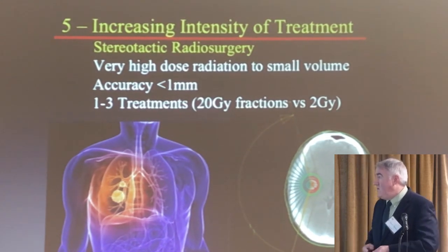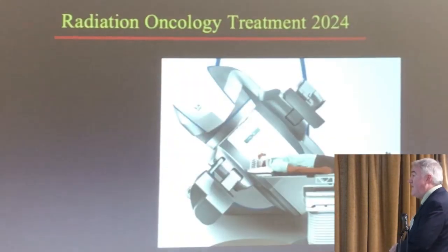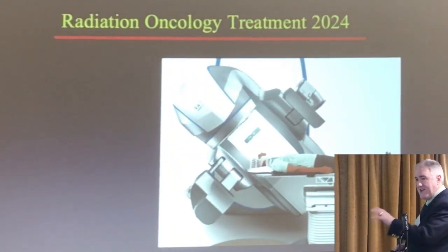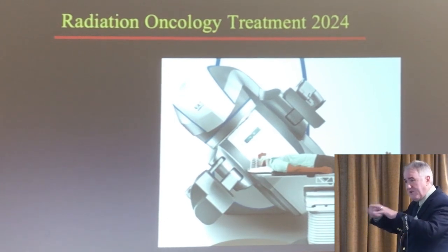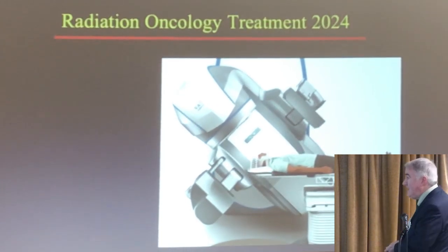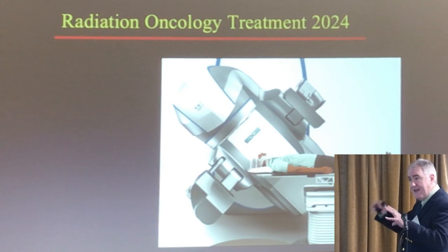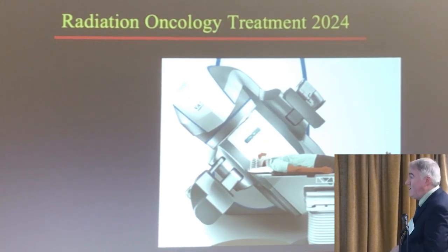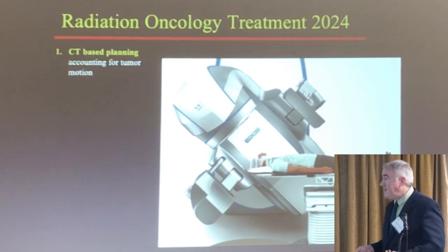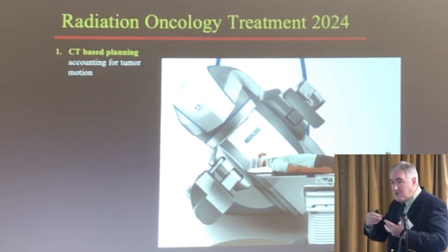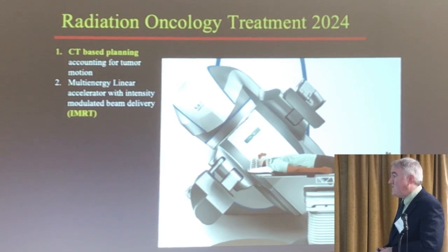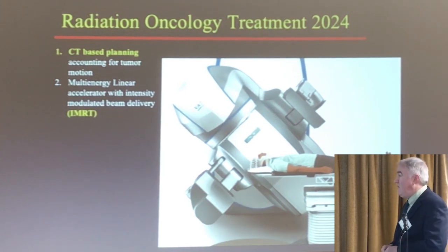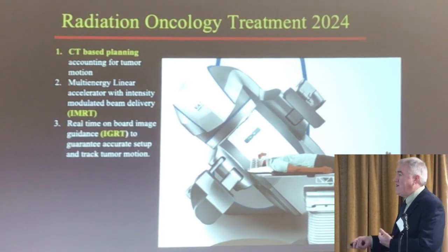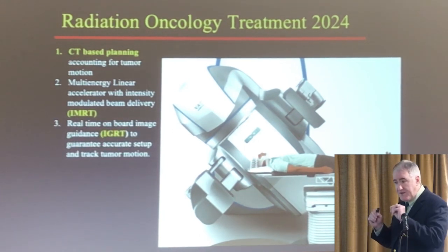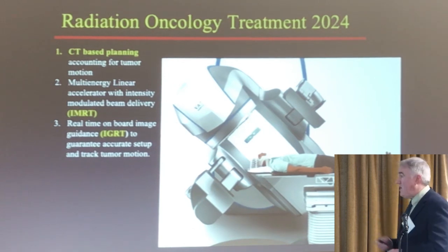So in summation, treatment in 2024 looks like this. You come in, you lay down on a table, you're on a special couch that has what we call 6 degrees of freedom. We can control this to within a millimeter accuracy in any dimension. The machine delivers a beam of radiation from this area. There's a targeting system that can actually monitor you and take x-rays of you while you're going through the treatment. So we use CT-based planning to account for the tumor motion that you might have. We can pick the energy that is most ideal for the treatment plan that we have, and we deliver it using that intensity modulation. We have real-time onboard imaging, what we call image-guided radiation therapy, to guarantee accurate setup and to make sure that we're always tracking the tumor to make sure it's being treated properly during therapy.